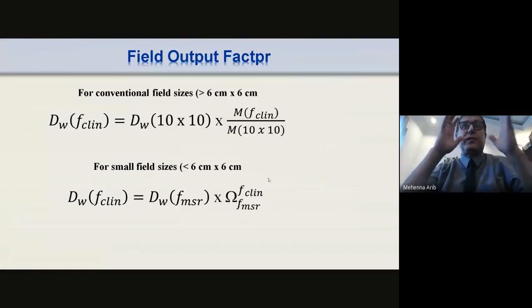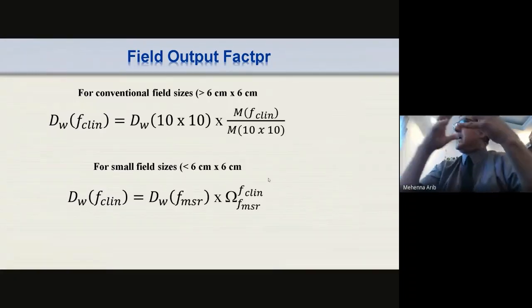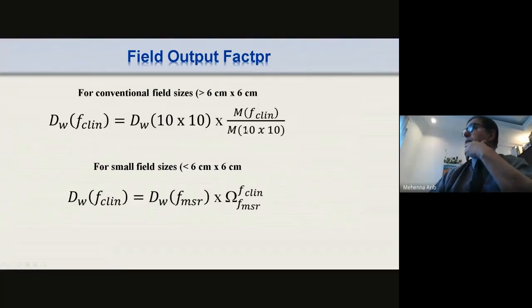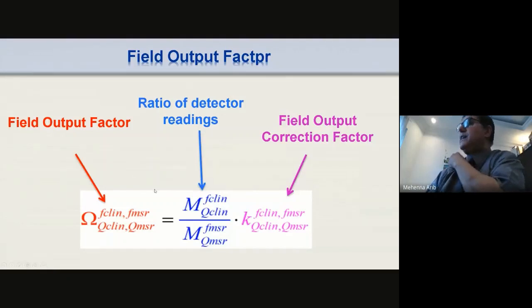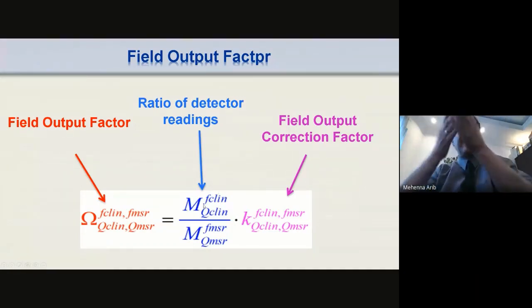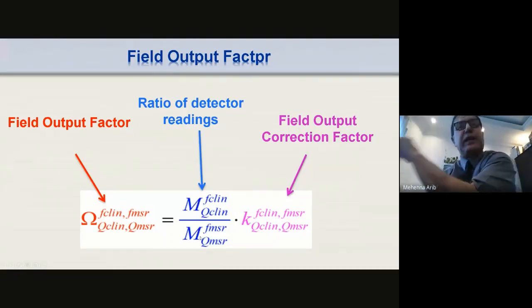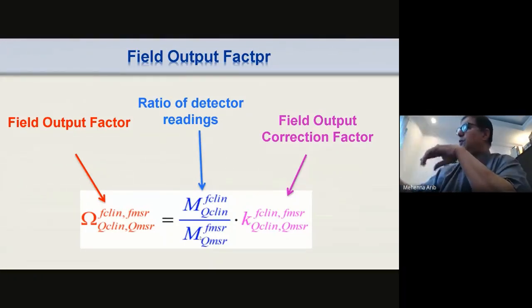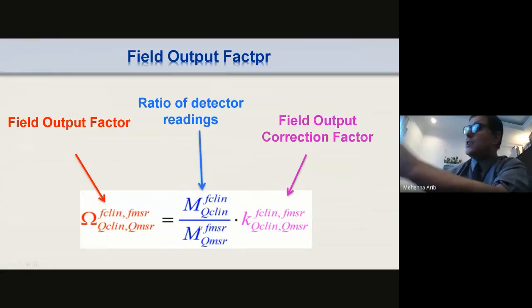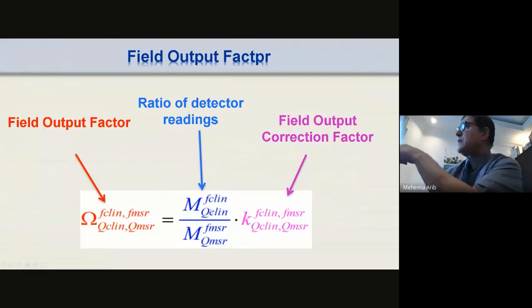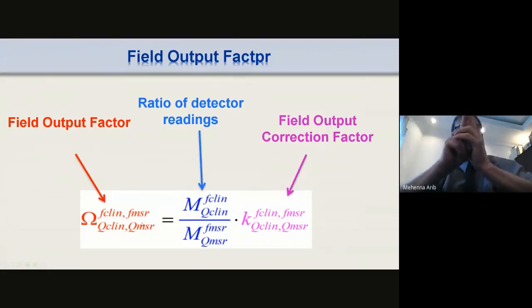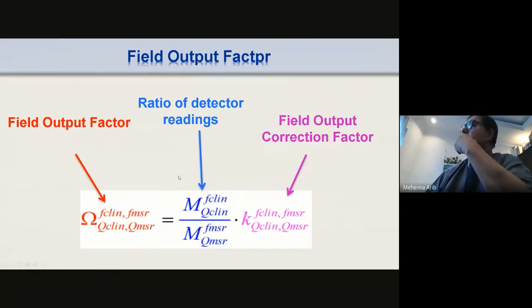Now we have the TPR. Let's move to the second part, which is the FCLIN, the clinical dosimetry, which consists of measuring the field output factor. So this is the output factor, our conventional output factor. But to get all the output factors aligned for all the detectors, for each detector you need to correct with the field output correction factor, which is published in the TRS 483. So for each detector, you measure the ratio of the readings, and then for that specific field size you multiply by the corresponding field output correction factor, and you get the field output factor, which is used for actually calculating the dose in clinical fields.